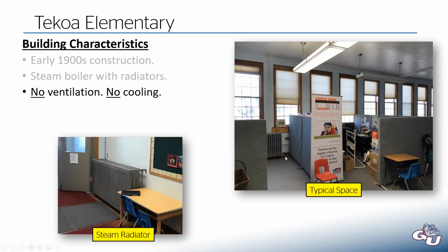They didn't have any ventilation, which we talked about on day one. Providing ventilation is a big deal. They also didn't have any cooling systems. Now, the code does not require you to have cooling systems. It doesn't require you to have air conditioning. But in a school building, even if they close in the summer, it can still be very, very nice to have cooling for, really, the beginning of the school year. So in late August and September, and at the end of the school year, right as we're going into summer, we can get some really hot days. And some schools, they just say, yeah, we don't need cooling. We'll just be hot for those few months.